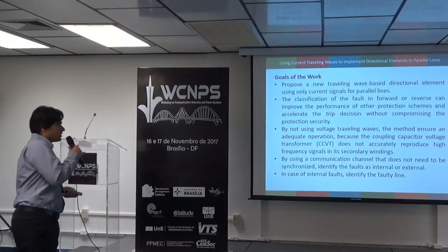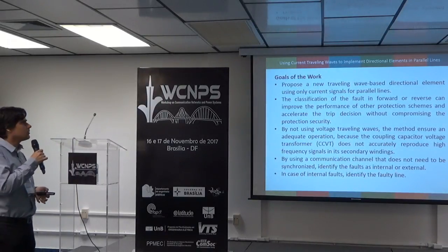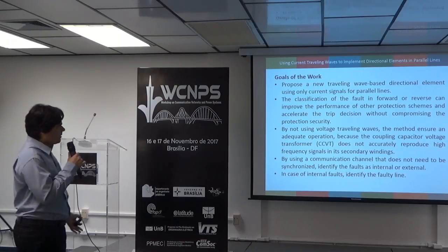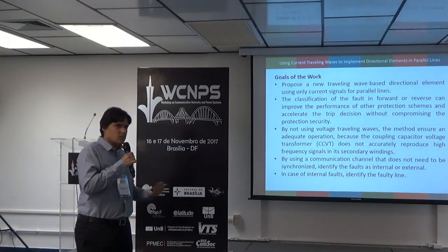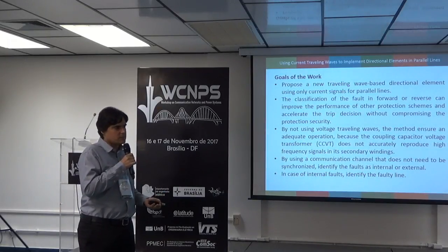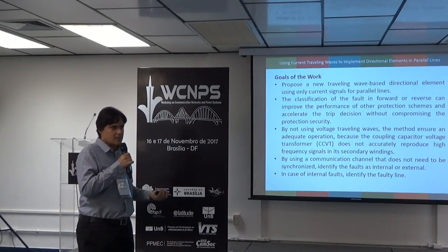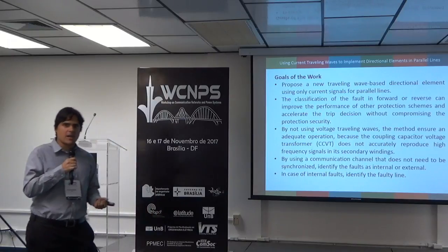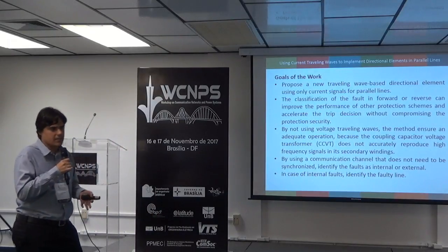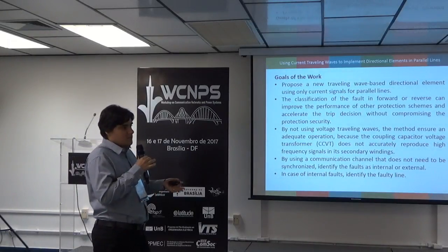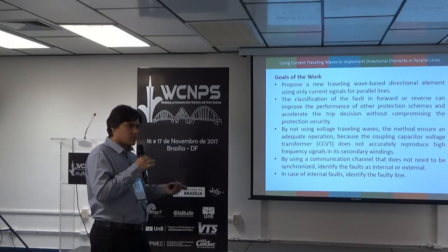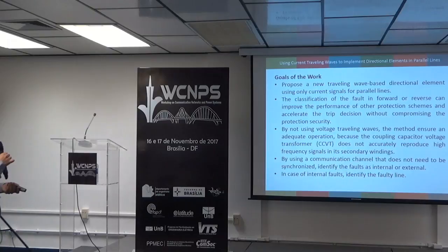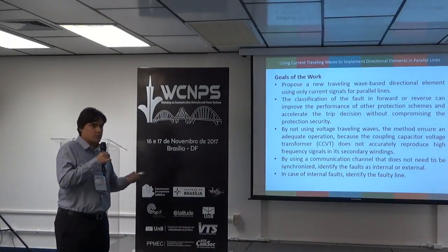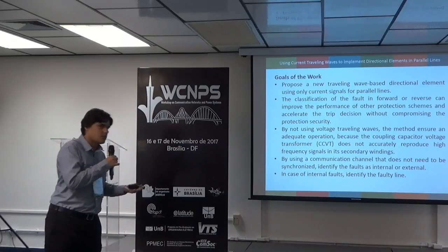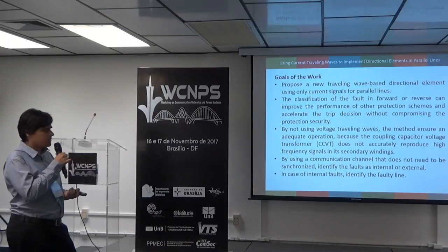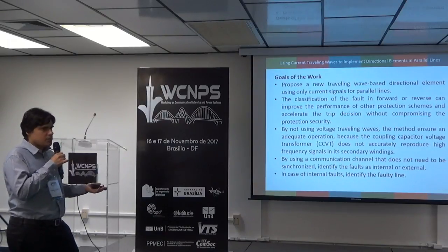The goal of the work is to propose a new traveling wave-based directional element using current signals for parallel lines. A method using voltage and current traveling waves has been proposed. The authors' argument is that the first voltage traveling wave can be accurately measured in time, not in amplitude, but in the vision of the authors, it's enough to promote an accurate fault direction. But as we know, the coupling capacitor voltage transformer does not accurately reproduce high frequency signals in its secondary windings. This is the motivation of the work.